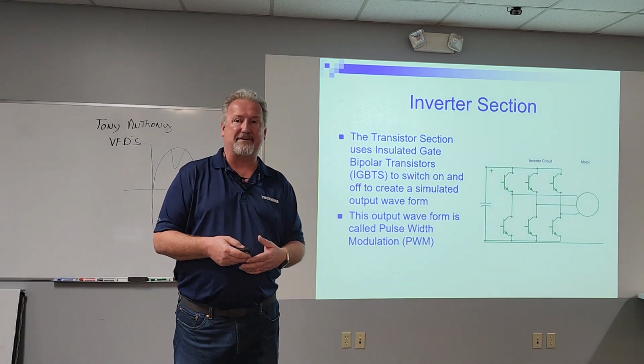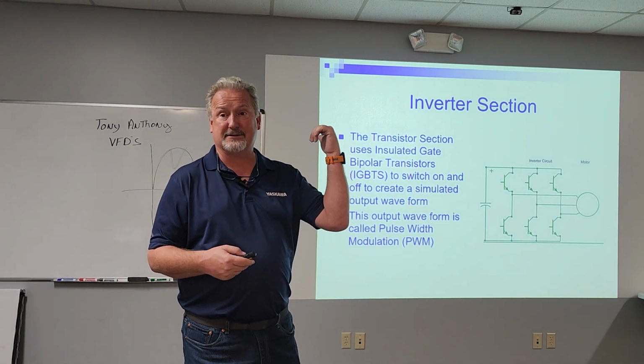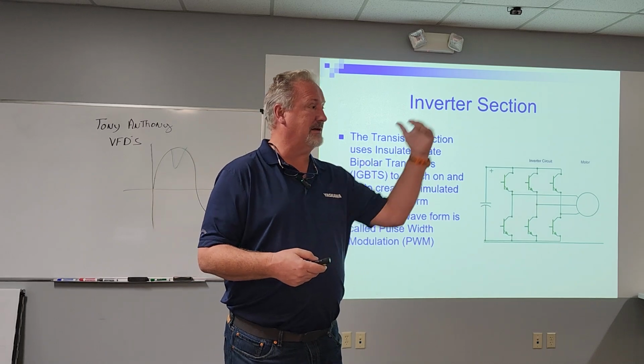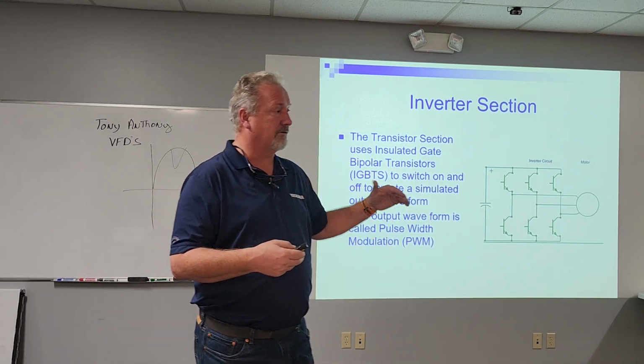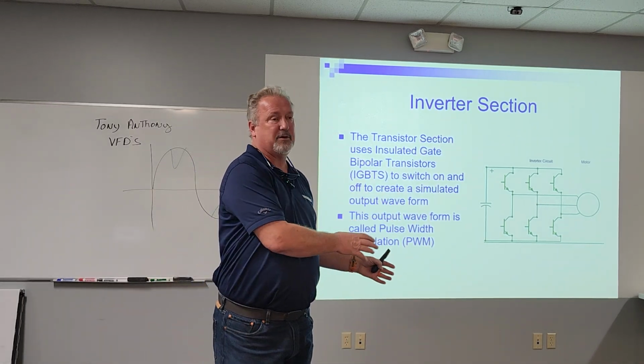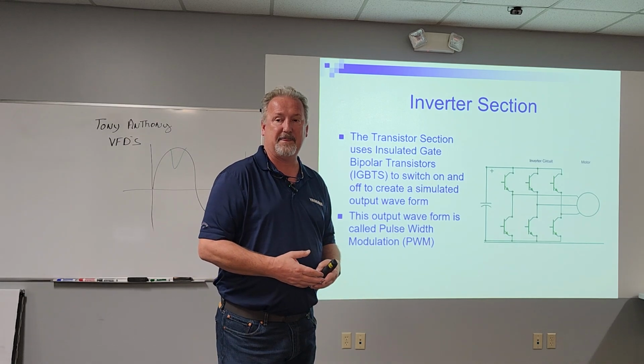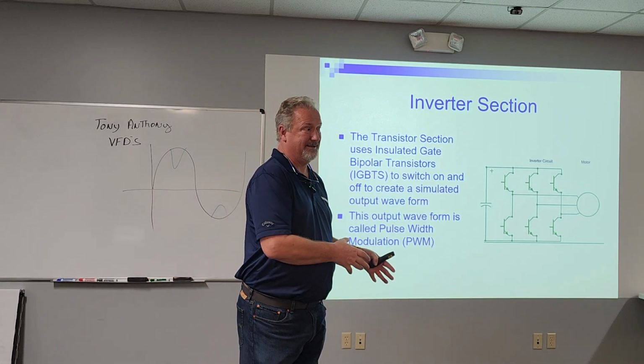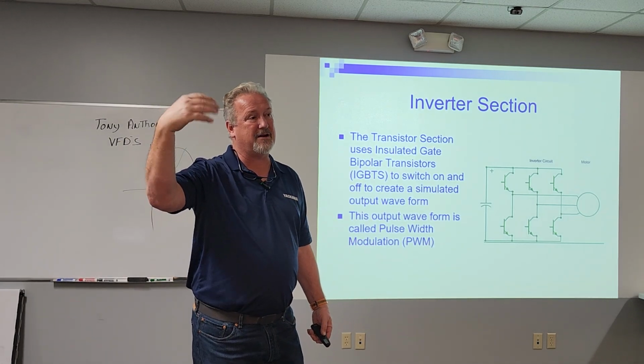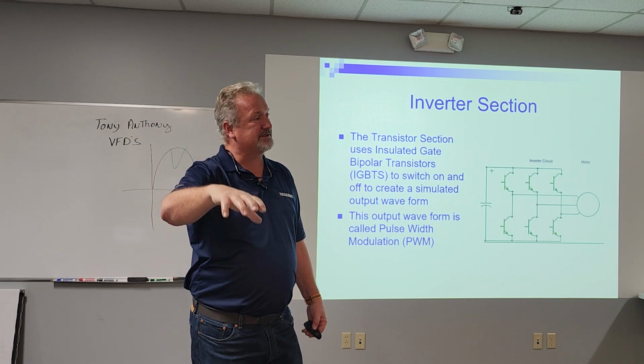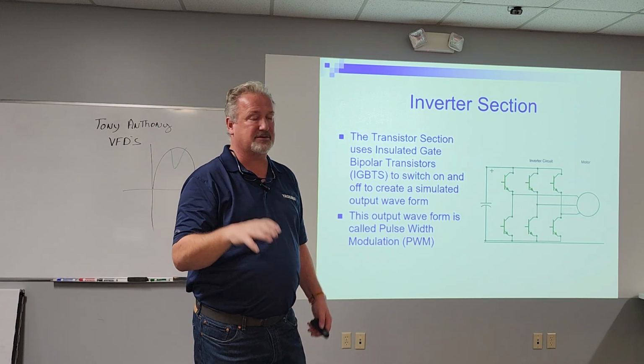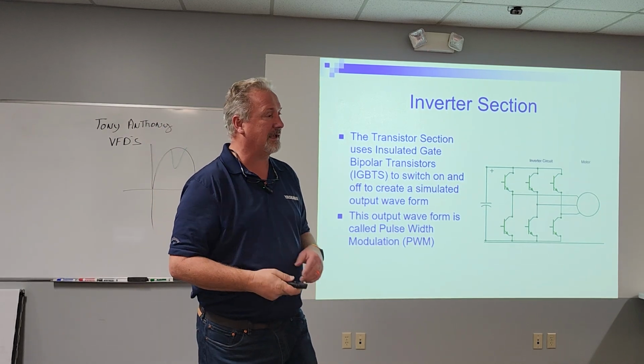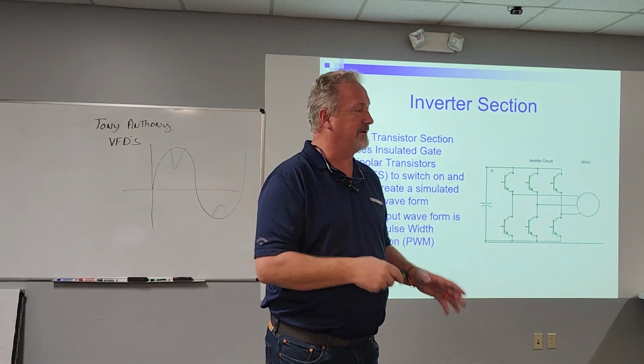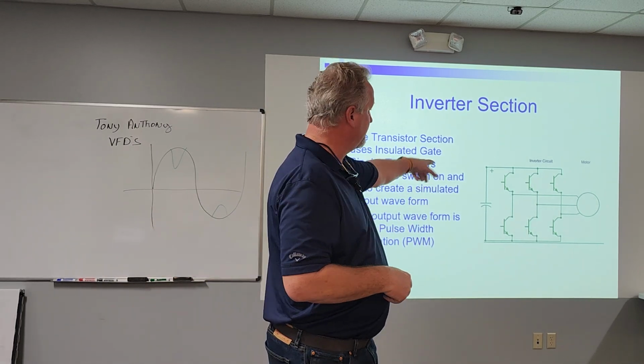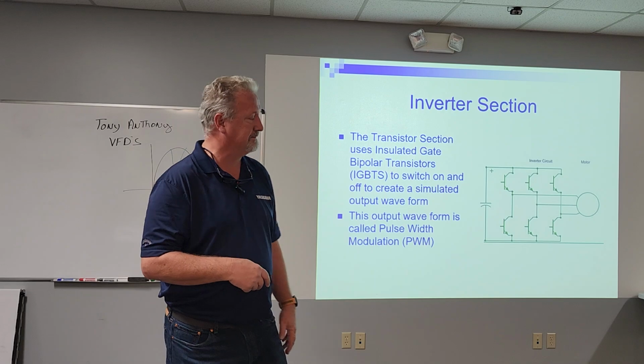Usually it's going to be around 4,000 or 5,000 times a second we're firing these. So maybe you can raise it up to 6 or 7, or drop it down to 2. The lower the carrier frequency number, the lower pitch that sound's going to be, but you also have more torque. The more often we fire those, it'll lower the sound, but we won't have as much torque. So there's a nice fine line you've got to make sure you're looking at. But you can actually change the sound of the motor by changing how often we're firing these to create those sine waves.